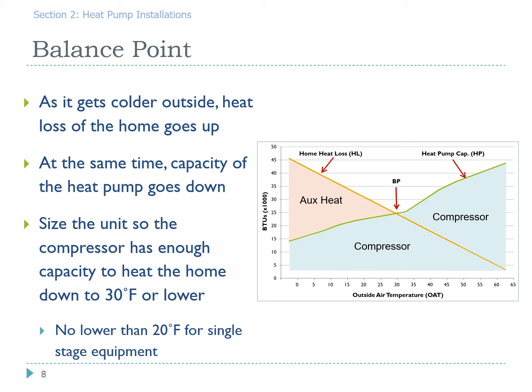And then at the same time, the capacity of the heat pump goes down. That's indicated by the green line. So the compressor can heat anything below that green line. And then when the balance point is met, that's the point at which the compressor can no longer heat the home, then auxiliary strip heat is needed.